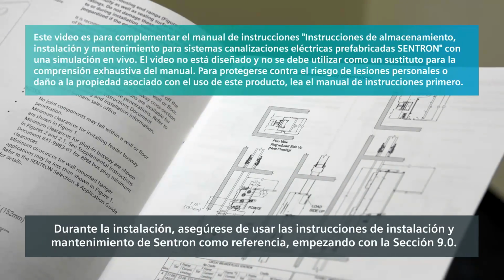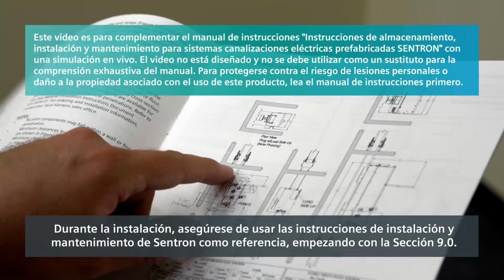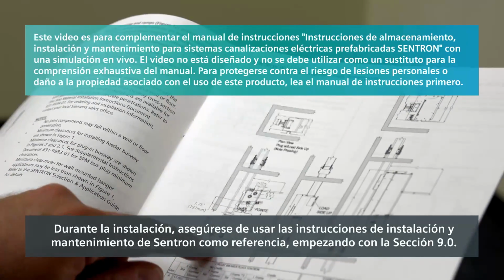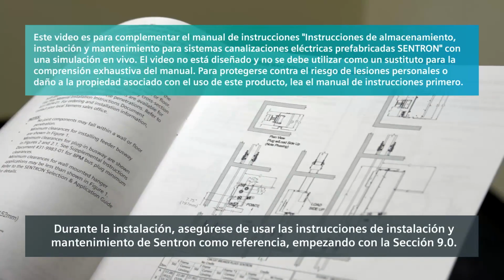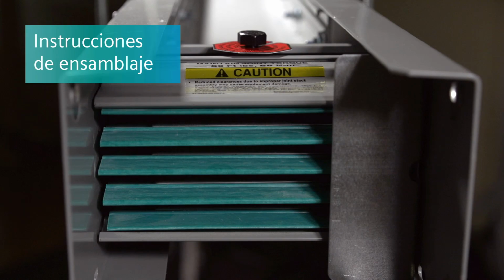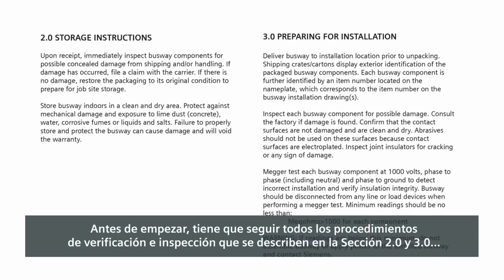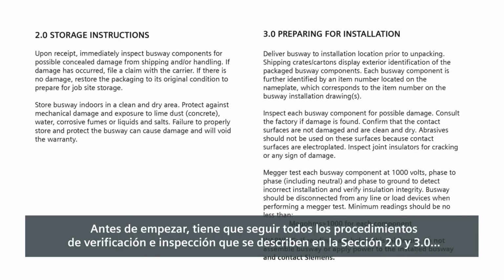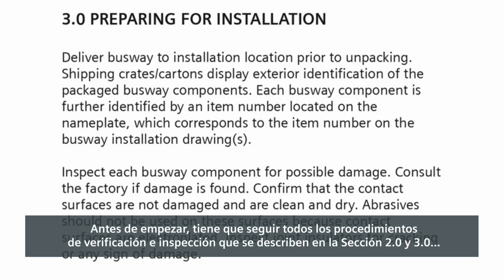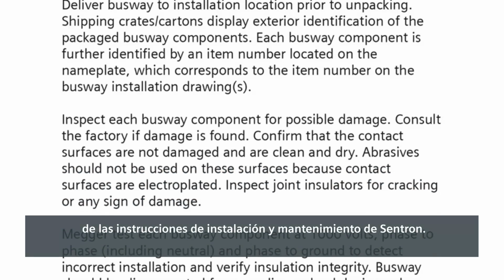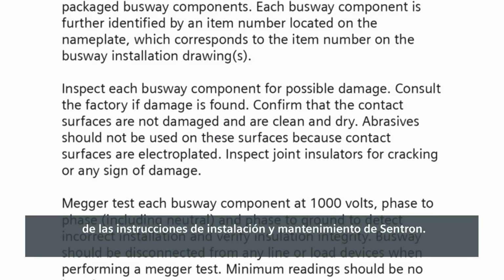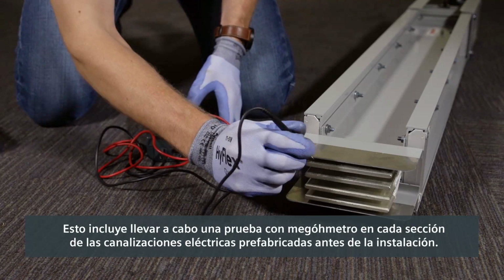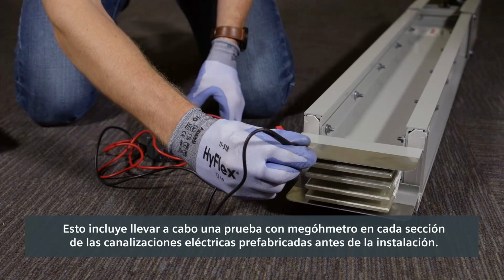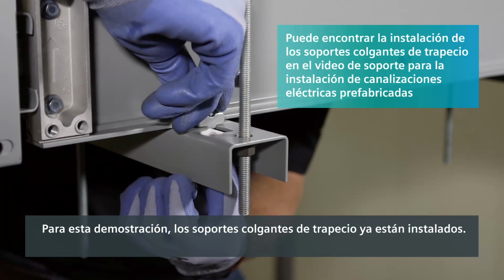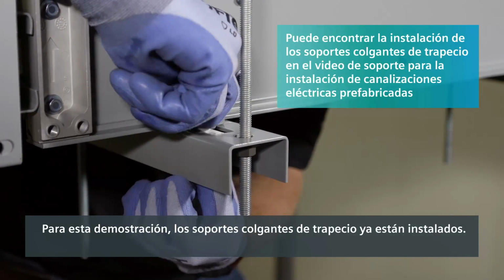Throughout the installation, make sure you use the Sentron installation and maintenance instructions for reference, beginning with section 9.0. Before you begin, you must follow all checkout and inspection procedures described in Section 2.0 and 3.0 of the Sentron Installation and Maintenance Instruction. This includes conducting a Megger test on each section of busway before installation. For this demonstration, trapeze hangers have already been installed.